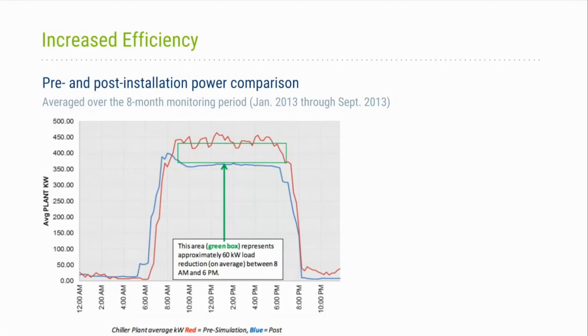We had 2 weeks in March of 2013 and 2 weeks in September where we configured the plant to be basically a constant volume operation. Because some things were modified, that required the VFDs to be put at full speed, and some isolation valves had been added to the design. Those had to be put back in a full open position. Other things were modified in the control code. So it was probably a 90% accurate simulation over a 2-week period in March for a winter simulation, and then 2 weeks in August.